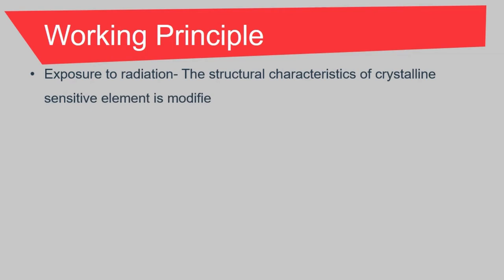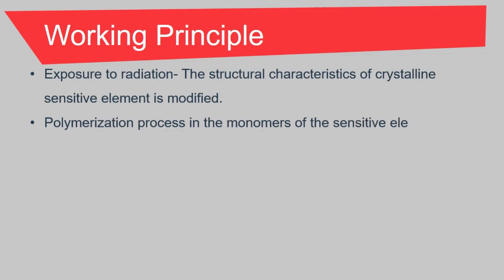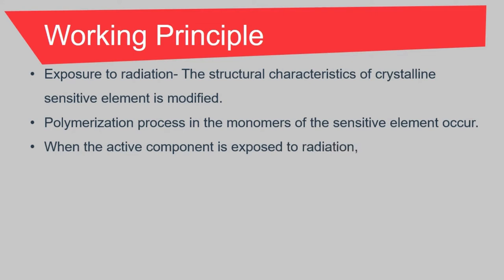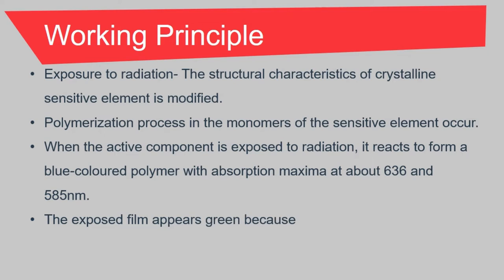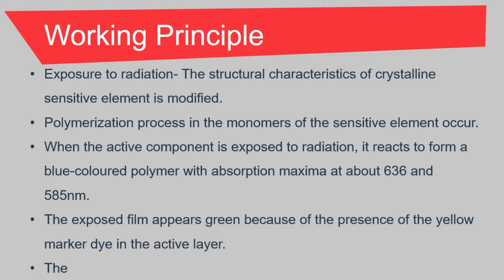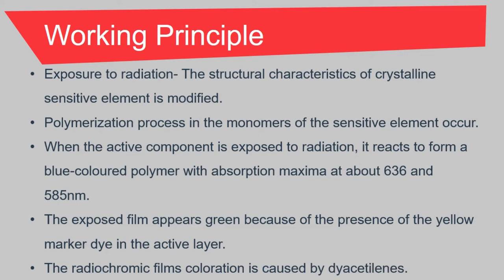Working principle. First is exposure to radiation. When the film is irradiated, the structural characteristics of the crystal sensitive element are modified. This causes a polymerization process in the monomer of the sensitive element to occur. When the active component is exposed to radiation, it reacts to form a blue-colored polymer with absorption maxima around 636 and 585 nanometers. The exposed film appears green because of the presence of a yellow marker dye in the active layer. The radiochromic film coloration is caused by diacetylene, a type of crystalline polyacetylene that is very sensitive to ionizing radiation.